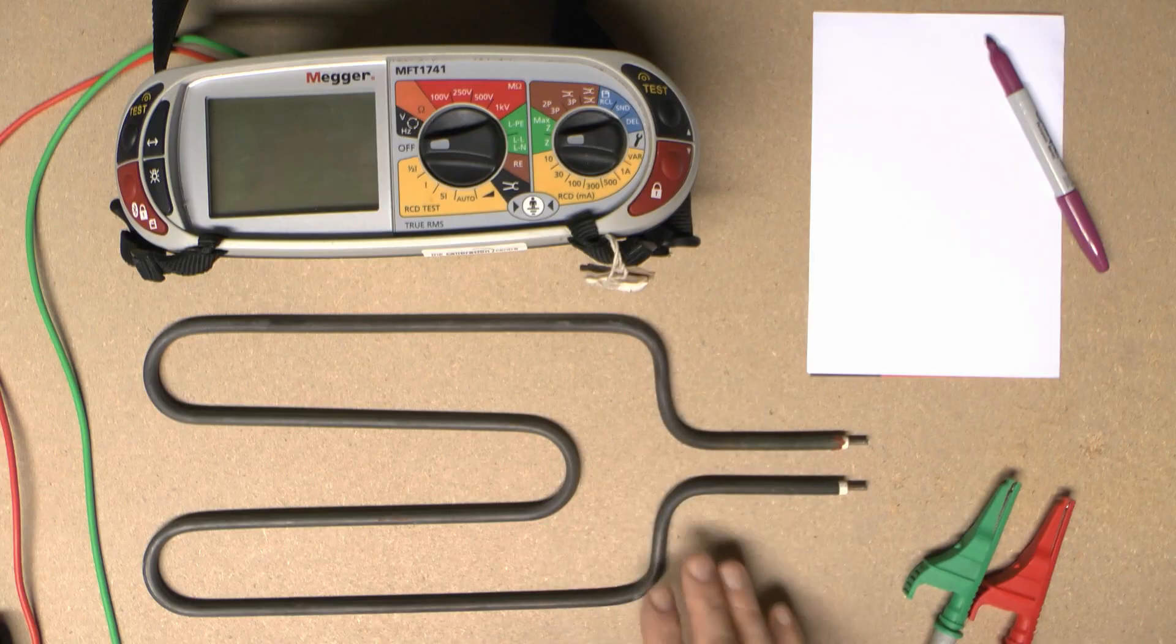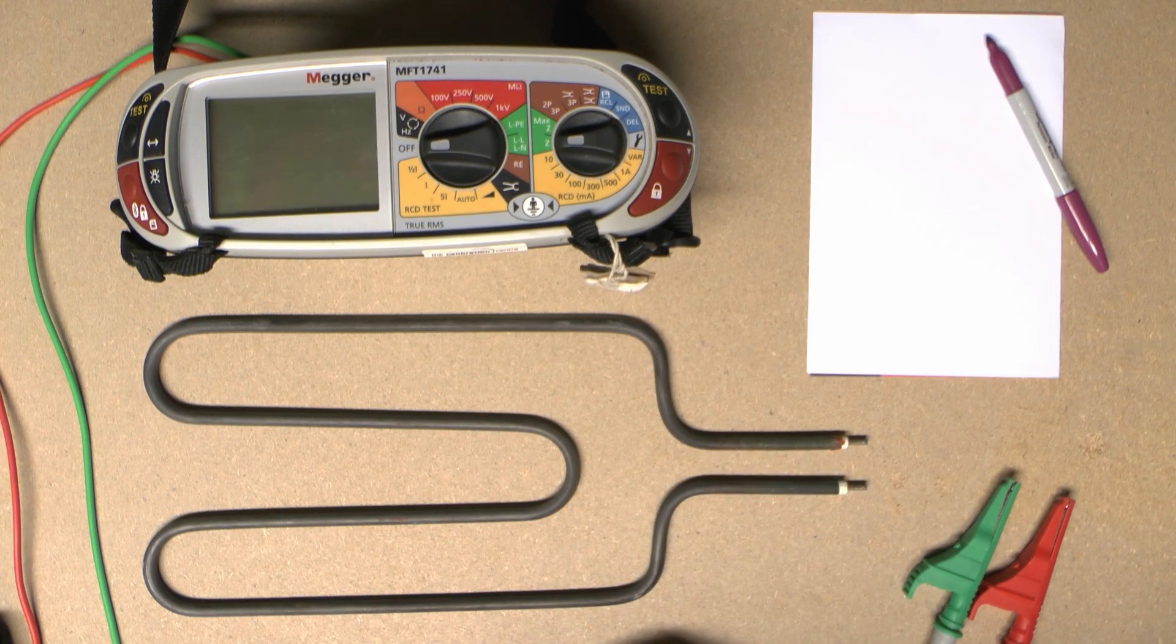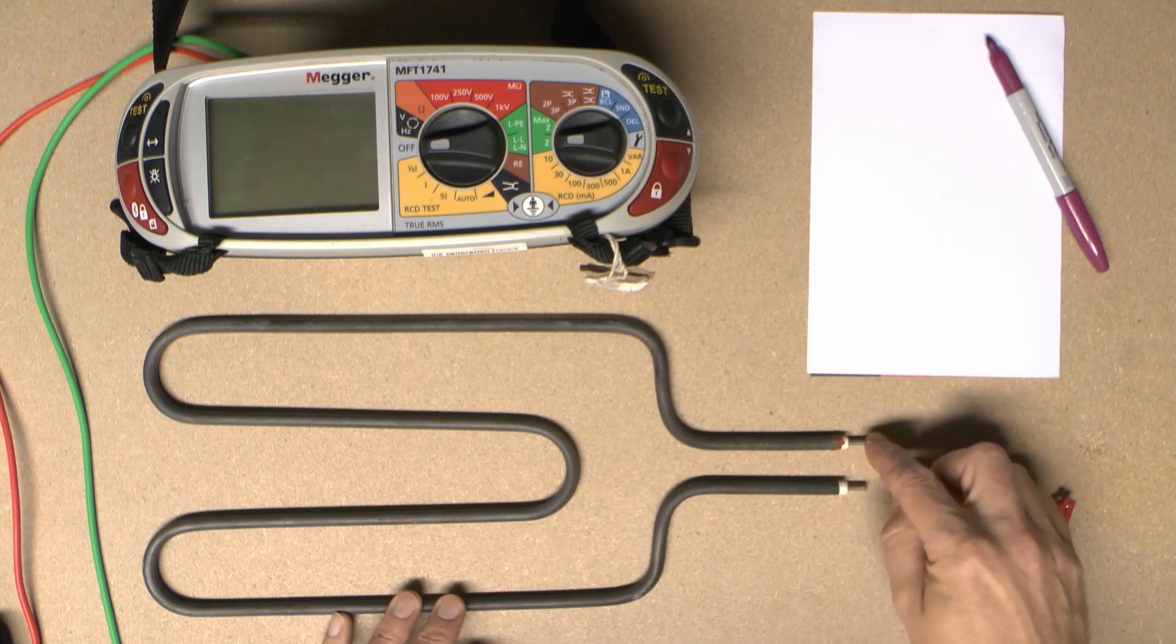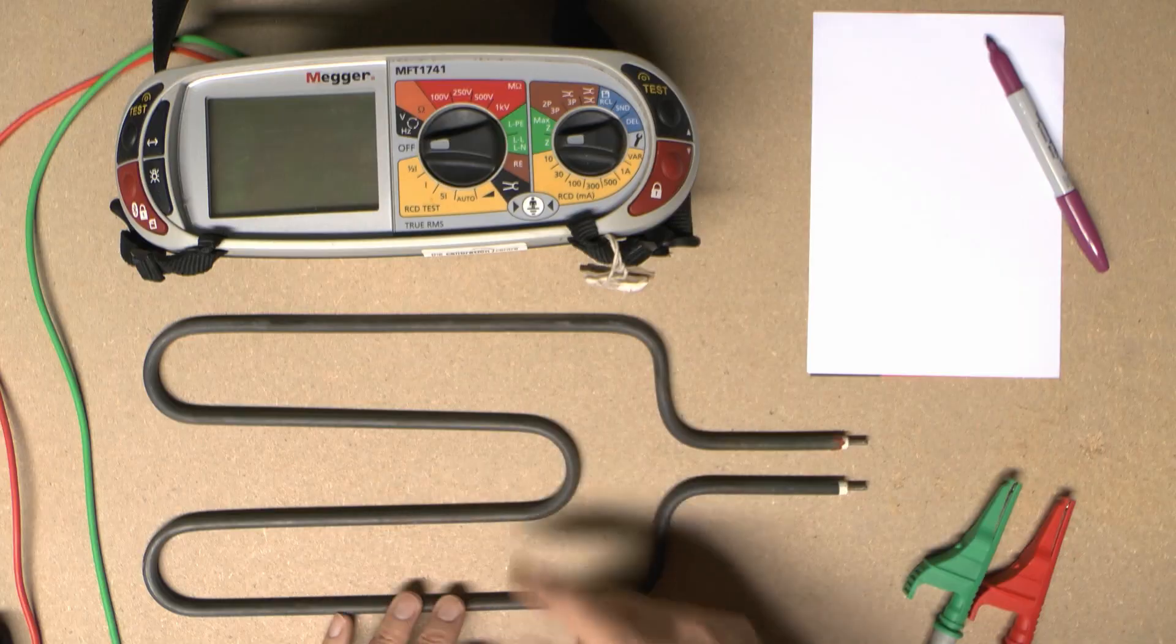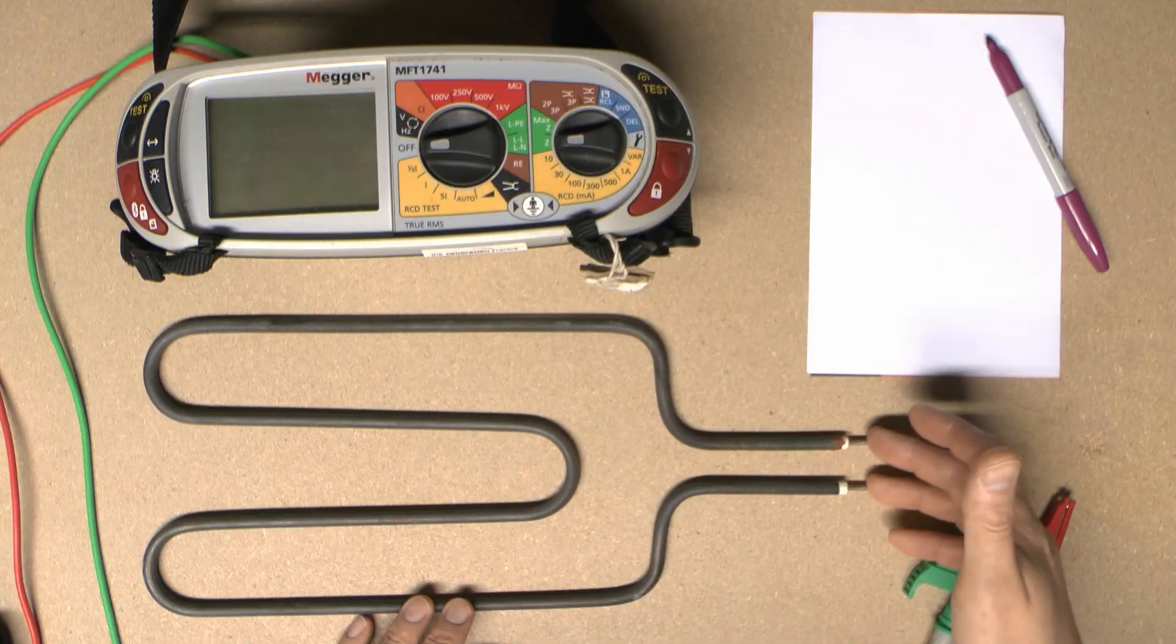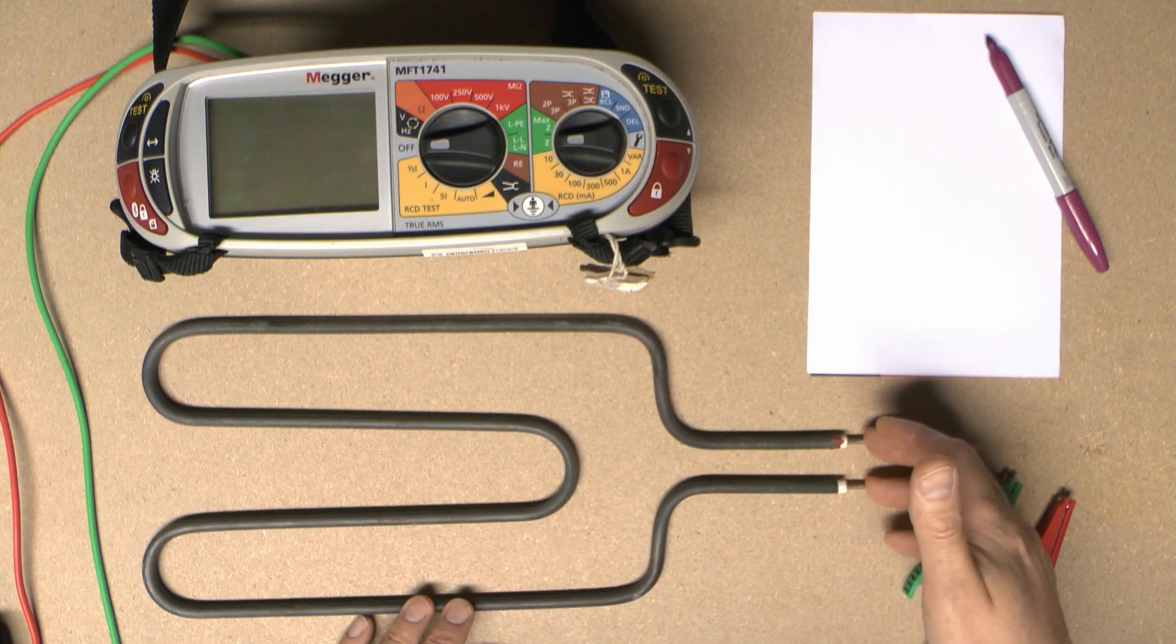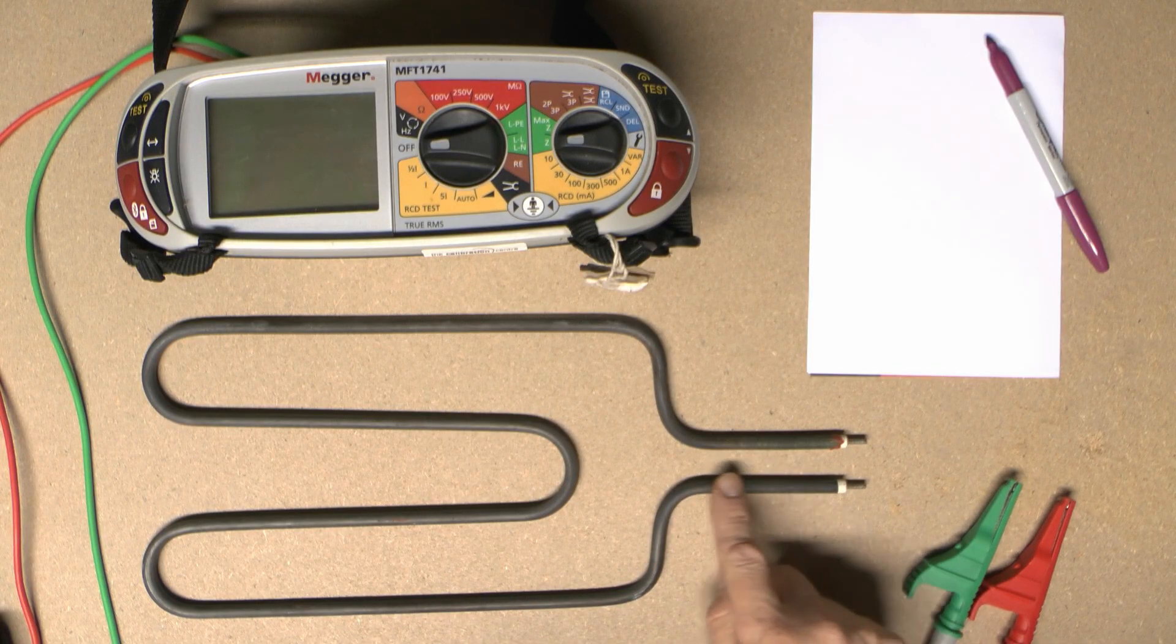We've got a heating element here from a storage heater, but all elements are pretty much the same in construction. You have two pins or connections at one end, line and neutral, and it doesn't matter which way round those go because it's just a resistive wire inside. Then you have some kind of metallic covering over the whole thing. You should have a certain amount of resistance between the two pins where electricity is connected, and basically nothing between the pin and the metallic covering.